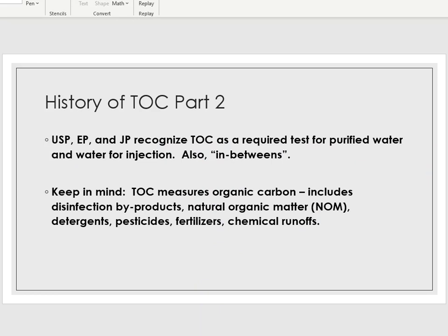More history of the TOC analyzer. The TOC was also approved by the USP, and that's something that we've talked about before in this class already. The United States Pharmacopoeia, the European Pharmacopoeia, and the Japanese Pharmacopoeia. The USP, the EP, and the JP all recognize TOC as a required test for purified water and water for injection within a pharmaceutical laboratory.